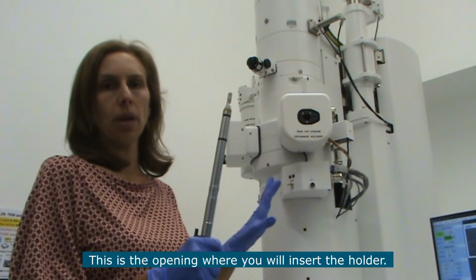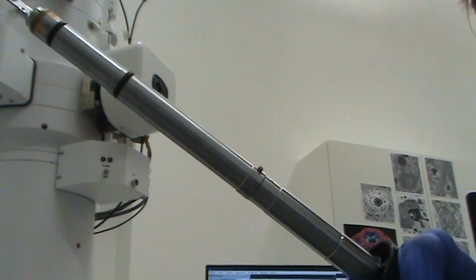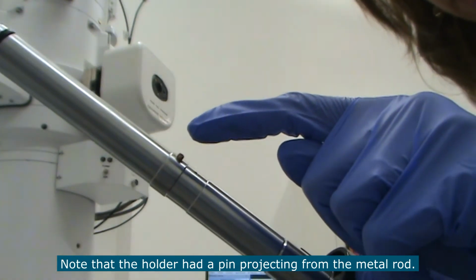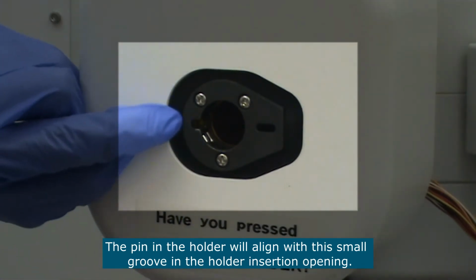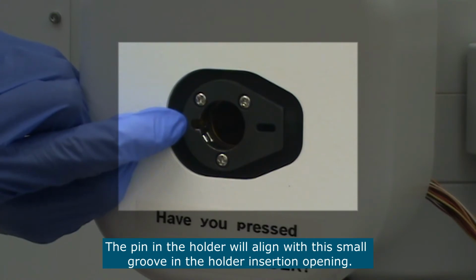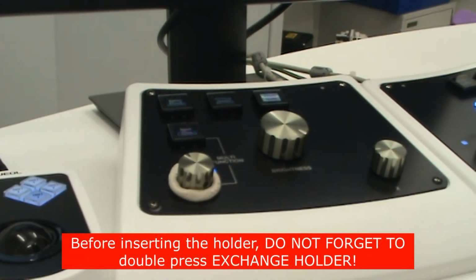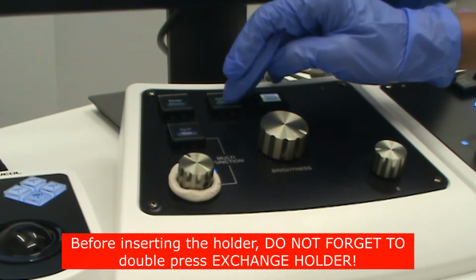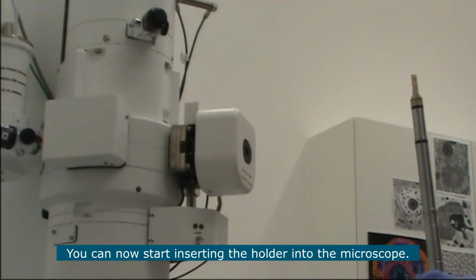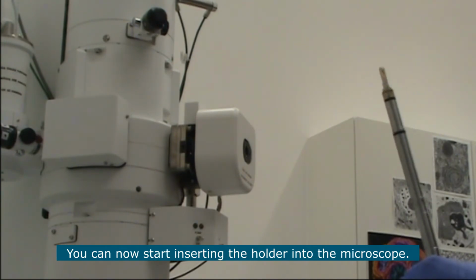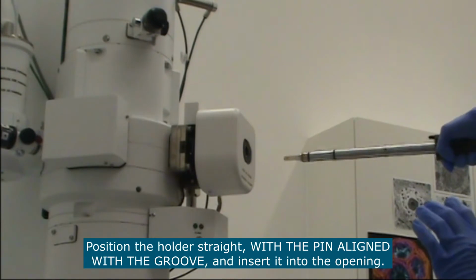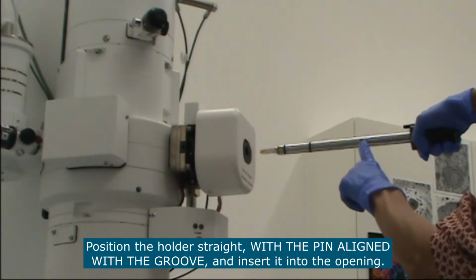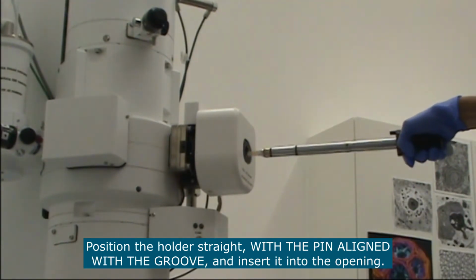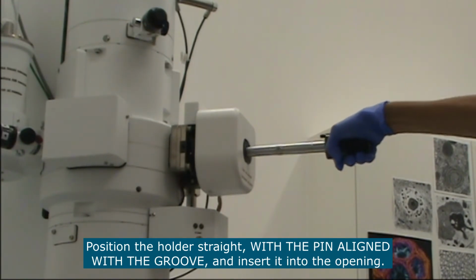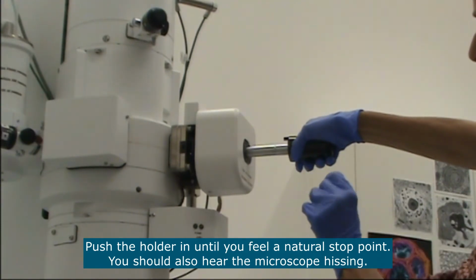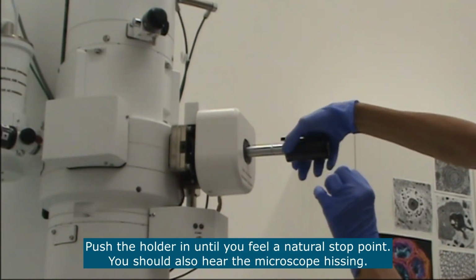You will now insert the holder in the microscope via this opening here. You will notice that the holder has a pin right here. The pin in the holder will align with this small groove in the opening where you will insert the holder. Before you insert the holder into the microscope column, make sure you double press exchange holder. You should hear a noise. So now you can start inserting the holder into the microscope. Hold the holder firmly and straight, making sure that the pin is aligned with the groove in the opening. Once the pin gets inside the groove, push it a little bit until it makes a gas noise.